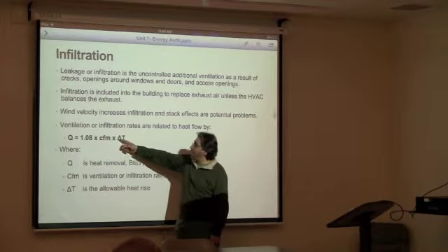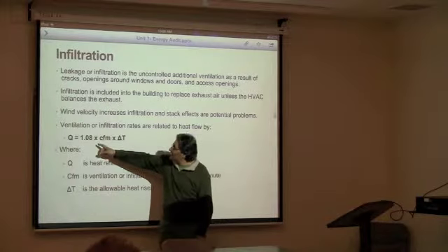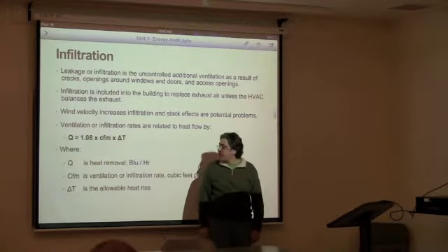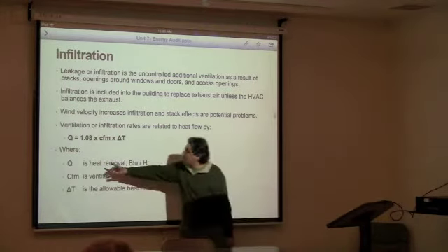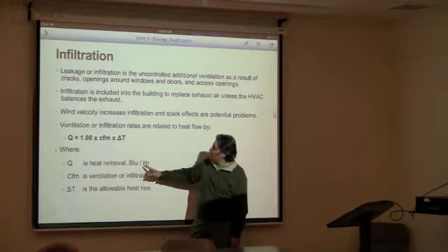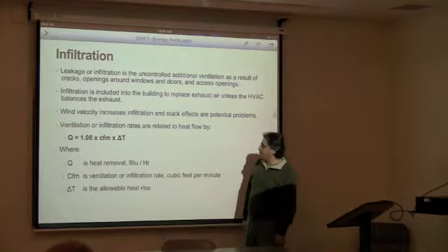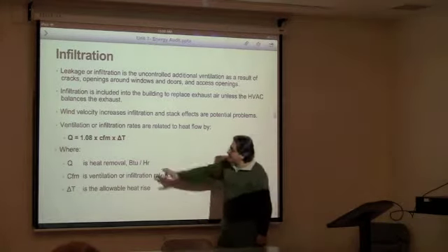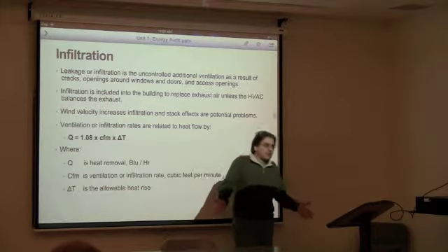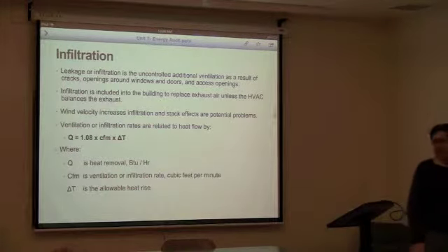So in summertime, you're adding heat. In winter time, you're cooling down the place. Multiplied by 1.08, it gives you the total amount of power that you're losing as BTU per hour. Right? Now, you might say the delta T is easy because I know what's the temperature outside, I know what's the temperature inside, those things are recorded very easily.